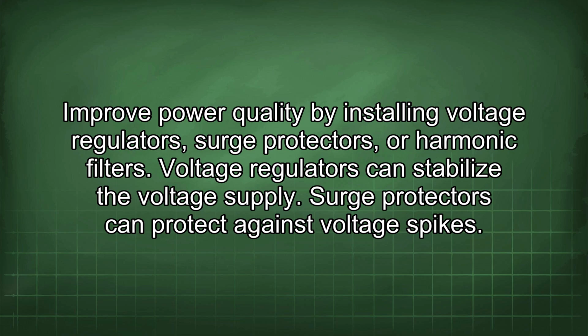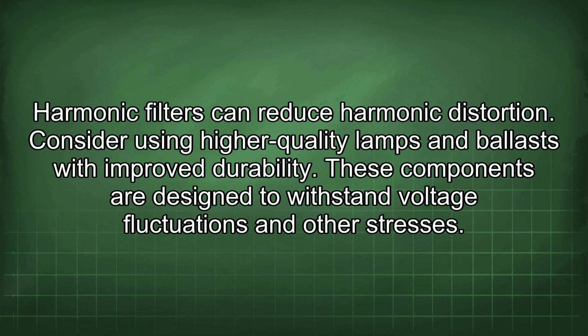Voltage regulators can stabilize the voltage supply. Surge protectors can protect against voltage spikes. Harmonic filters can reduce harmonic distortion. Consider using higher quality lamps and ballasts with improved durability. These components are designed to withstand voltage fluctuations and other stresses.